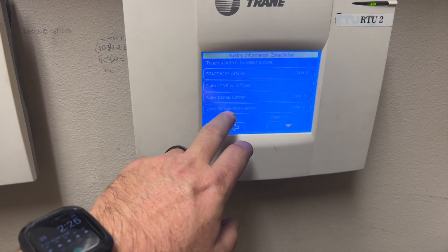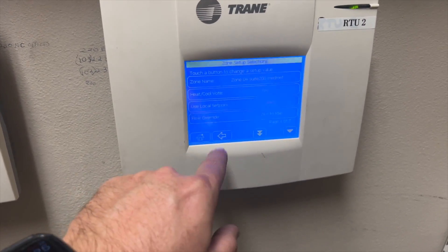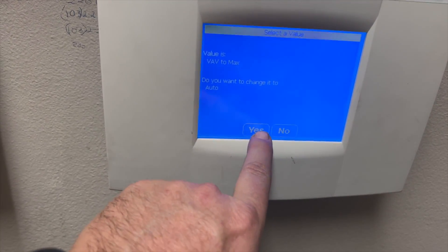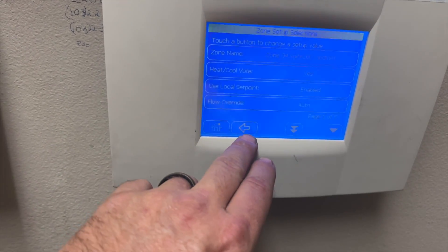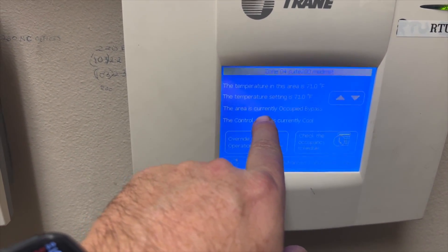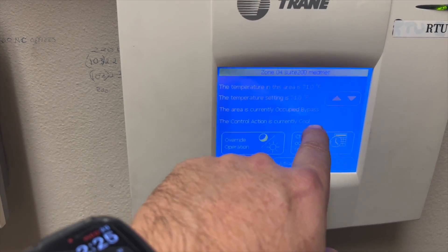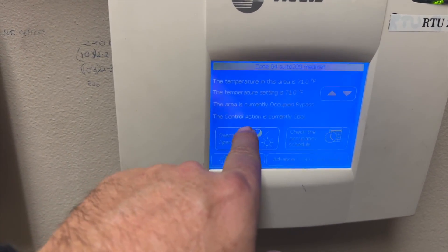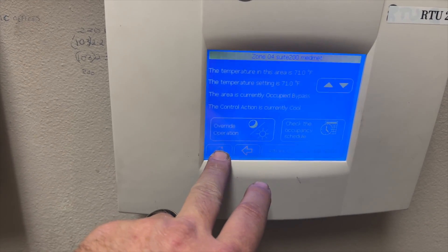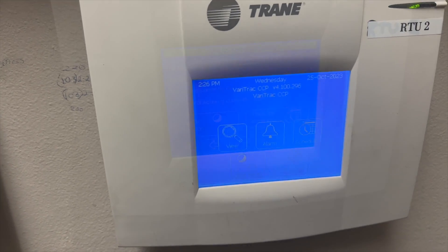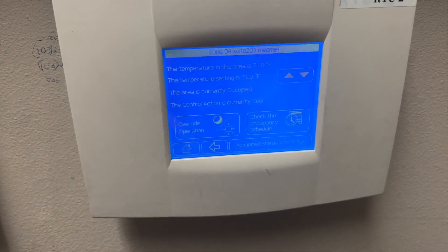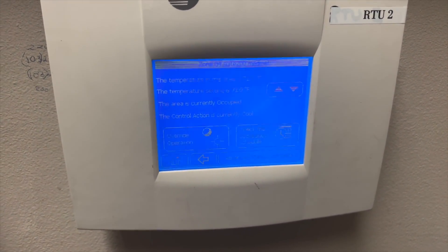We want to go ahead and put this back into normal mode. Flow Override — put it back to Auto. Now it's back on auto, currently set at 71. The area is currently showing occupied bypass, so we need to give it a minute and it'll eventually show just occupied. It's currently in cooling mode so we should be good. Now it says Occupied — occupied bypass means I was bypassing stuff, and it just takes a minute or two to reset.